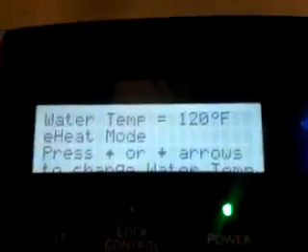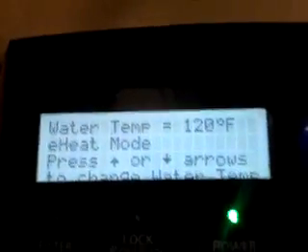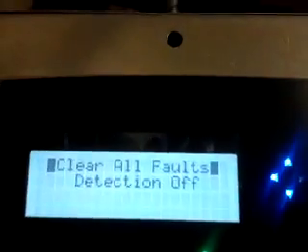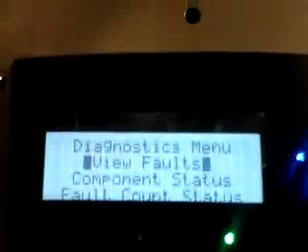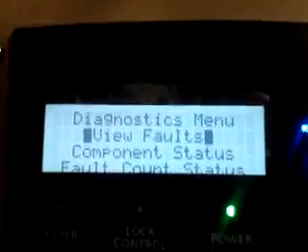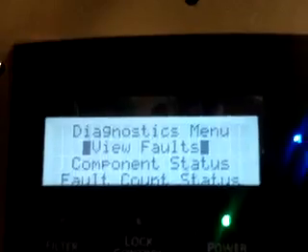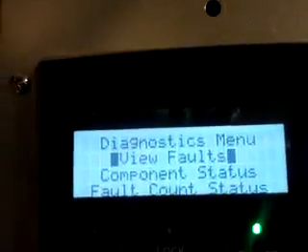This is how to get into the diagnostic menu of your heat pump water heater. First, press eHeat Mode, then press Enter, scroll down to Diagnostic Menu. You can choose component status, fault count, or whatever you want. You can clear them. The password is Filter, Lock, Control, and Vacation — those are the three buttons you have to press.